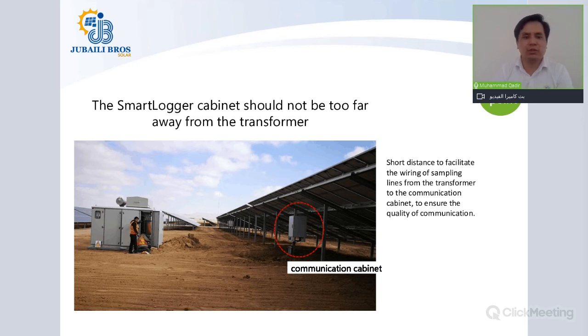The smart logger cabinet should not be too far away from the transformer. This slide is actually about the MBUS communication. When you're using MBUS communication, normally in projects for the MV termination, you have a transformer. Next to the transformer, you have an LV cabinet. From the LV cabinet, you will be taking two small cables going towards the smart logger to send the data of the MBUS. So you must keep the distance from the LV side of your transformer to the smart logger at the shortest. Short distance will facilitate the wiring of sampling lines from the transformer to the communication cabinet to ensure the quality of communication.